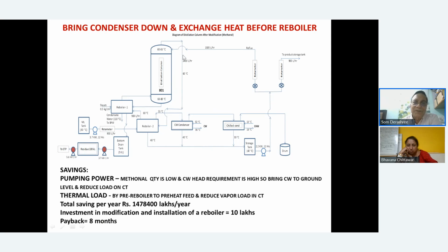Second thing, what we did was when we brought it down, the solvent which is coming at 30 degrees, we had another reboiler installed. So this reboiler actually acts as a condenser first. It heats up and preheats the reboiler. So reboiler 2 is actually a preheater to the existing reboiler 1. So your steam consumption will also come down. Your pumping requirement for both chill water and cooling water will also come down, and you save steam and power both. Almost 14 lakh was the saving per annum, and 10 lakh depending on the batch size, the number of batches that they were taking.